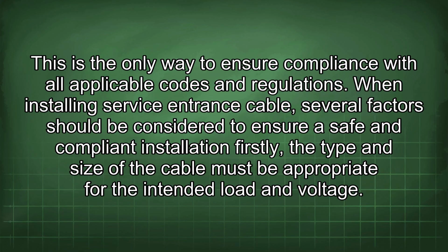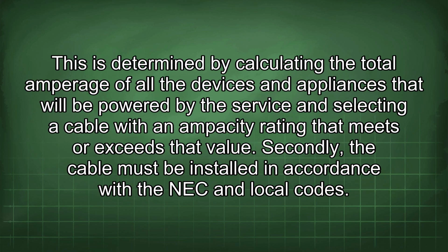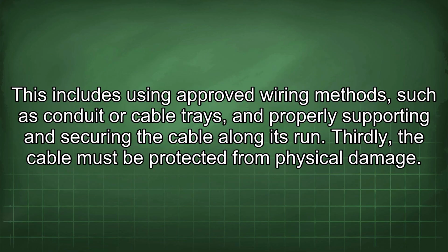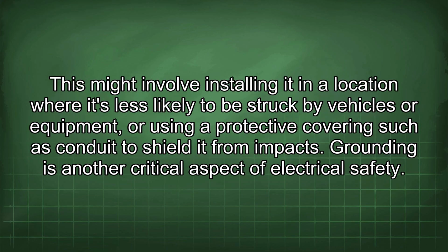When installing service entrance cable, several factors should be considered to ensure a safe and compliant installation. Firstly, the type and size of the cable must be appropriate for the intended load and voltage. This is determined by calculating the total amperage of all the devices and appliances that will be powered by the service and selecting a cable with an ampacity rating that meets or exceeds the value. Secondly, the cable must be installed in accordance with the NEC and local codes. This includes using approved wiring methods such as conduit or cable trays, and properly supporting and securing the cable along its run. Thirdly, the cable must be protected from physical damage. This might involve installing it in a location where it's less likely to be struck by vehicles or equipment, or using a protective covering such as conduit to shield it from impacts.